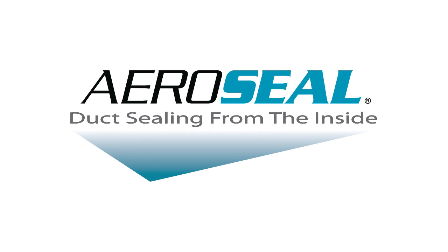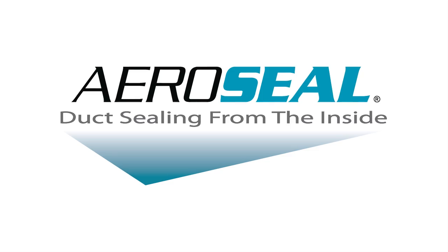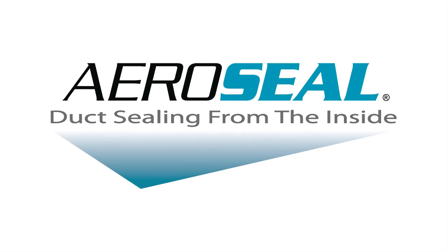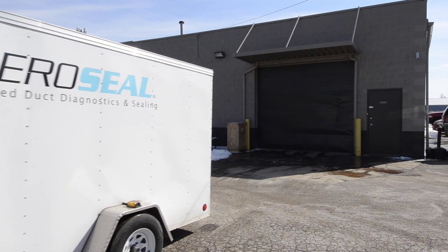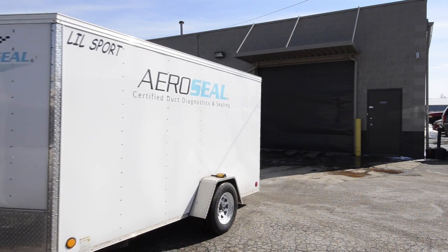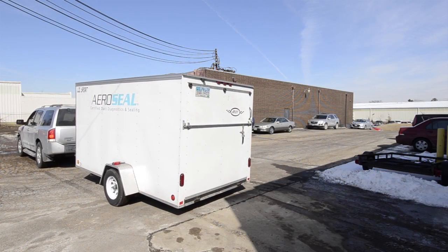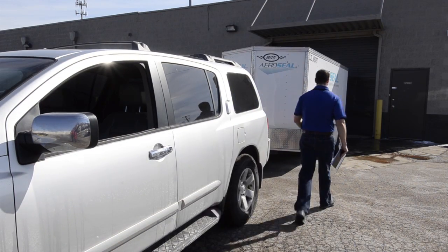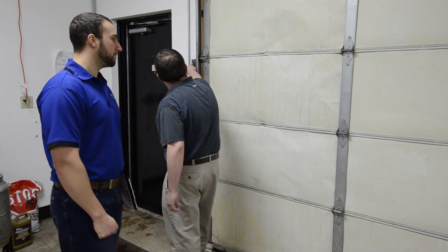Aeroseal is a commercial duct sealing solution. It seals leaking ducts from the inside. This means there is no breaking of the walls or ceilings. The Aeroseal process pressurizes the duct, measures the leakage, and injects micron-sized sealant particles into the holes where the air was escaping, creating a seal that will last for the lifetime of the duct.